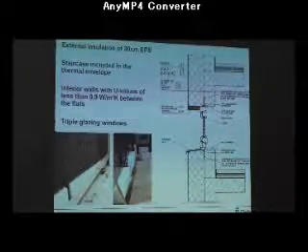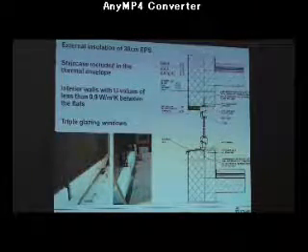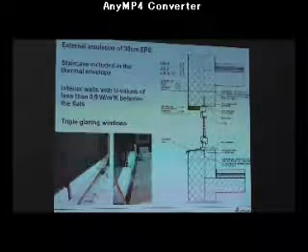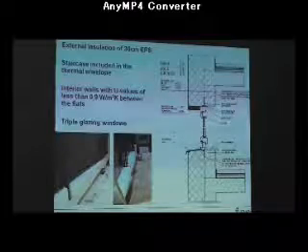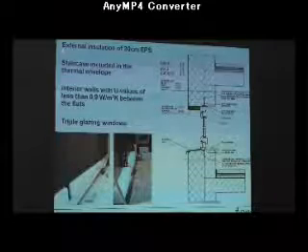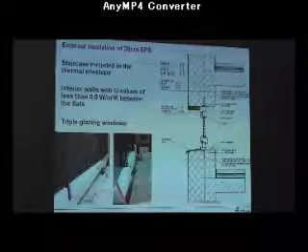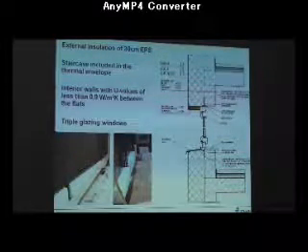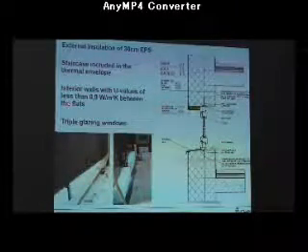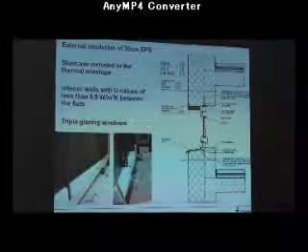As in other passive houses, in this project the first measure adopted is improving the performance of the building's envelope. These measures include external insulation of 30 centimeters of expanded polystyrene, the staircase included in the thermal envelope, interior walls between the flats with a U value of less than 0.9, and also triple glazing windows.